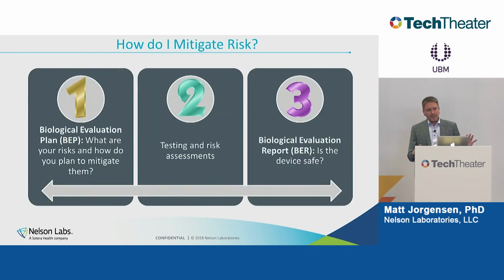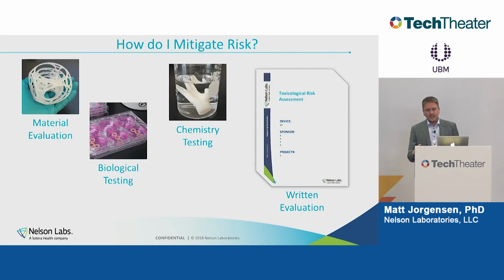After you make that plan, where there are gaps, we start to talk about testing and risk assessment. There are lots of different ways you could go about mitigating the risks identified in a biological evaluation plan: material evaluation, which hopefully comes up front and could be part of that plan itself, traditional biological testing, chemical testing, and straight-up written evaluations. In the past, biological testing was really the only option we'd consider. Now the landscape's opened up, and material evaluation, chemistry, and these written assessments are a lot more popular.